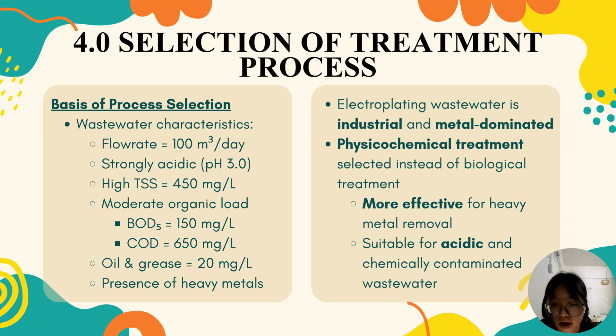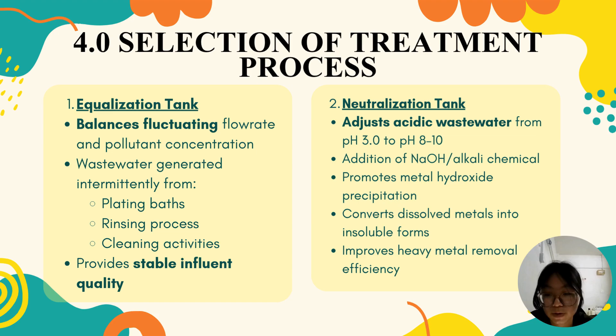The first treatment unit is the equalization tank, which balances fluctuations in wastewater flow rate and pollutant concentration. This is important because wastewater generation from plating and rinsing processes is intermittent. Next is the neutralization tank, where sodium hydroxide is added to increase the pH from acidic conditions to around pH 8 to 10. This promotes metal hydroxide precipitation and improves heavy metal removal.